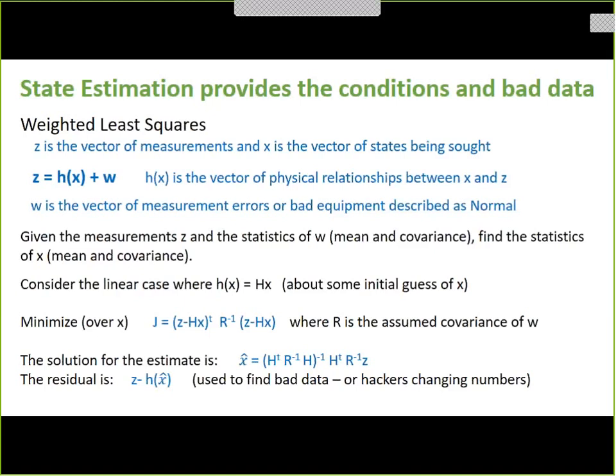Didn't use them. So Pete, is it accurate to say that when you say just believe the SCADA, the core assumption there is that the utility operators treat the SCADA measurements as the root of their assumption? In other words, it's their ground truth. And then everything else, like ACE calculations, AGC, state estimation, et cetera, are potentially errored, but the values are always the truth. Yeah, I'll get to the ACE thing in a second. But it's pretty simple. If you're an operator and you're measuring something and it's displayed on your computer, you believe it. You might be wrong. Maybe it is bad, but...